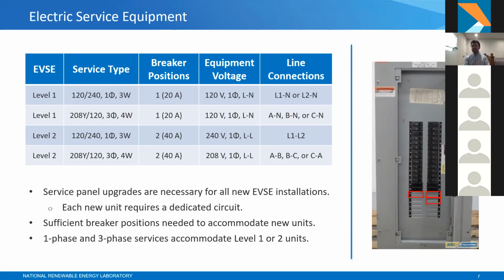And then beyond that, for level 2 units, because you're using a higher voltage, you actually need 2 separate breaker positions because you're going to make a little bit more of a complicated line-to-line connection as opposed to line to neutral. And you're getting that 240 or 208 volts out of there. So instead of just 1 breaker position, you'd actually need 2 breaker positions, and you'd be working with a double pole breaker that's typically rated at 40 amps for a 32 amp EVSE. Next slide.